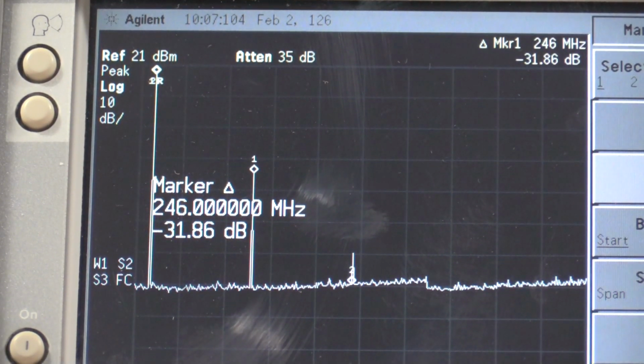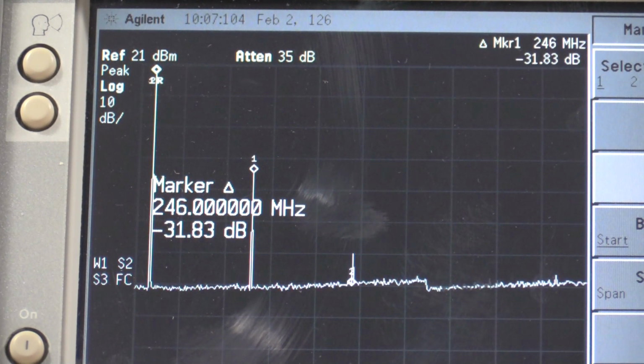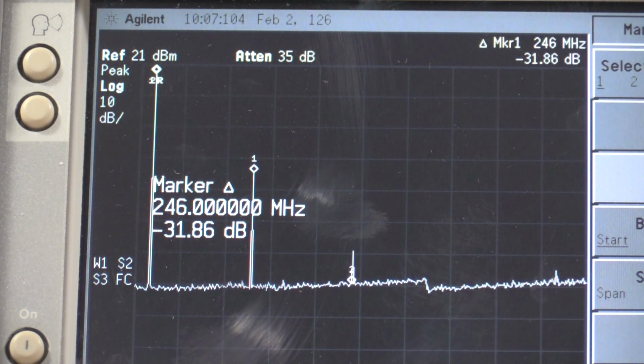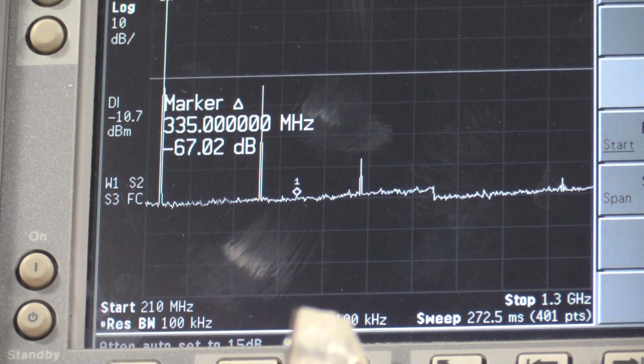Okay, I have to wind through the frequency again and just check the harmonic suppression, and I'm looking for delta markers. I need the main delta marker to be 27 dB down, and I need the third harmonic to be 42 dB down. So this needs to stay 27, that needs to stay 42, and I just have to run through the range again. Okay, everything is fine with the harmonics. I set the line here at the highest harmonics I saw, which I think was right around 31 dB, so that's fine. I have to get set up for the high range. We'll do it all over again.